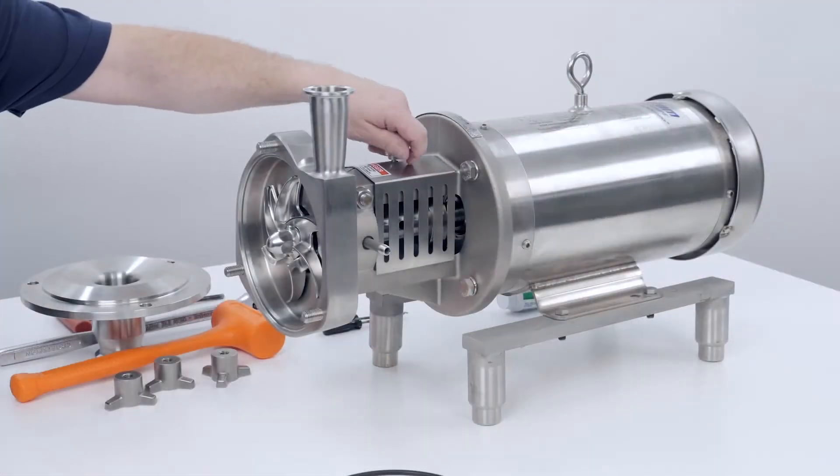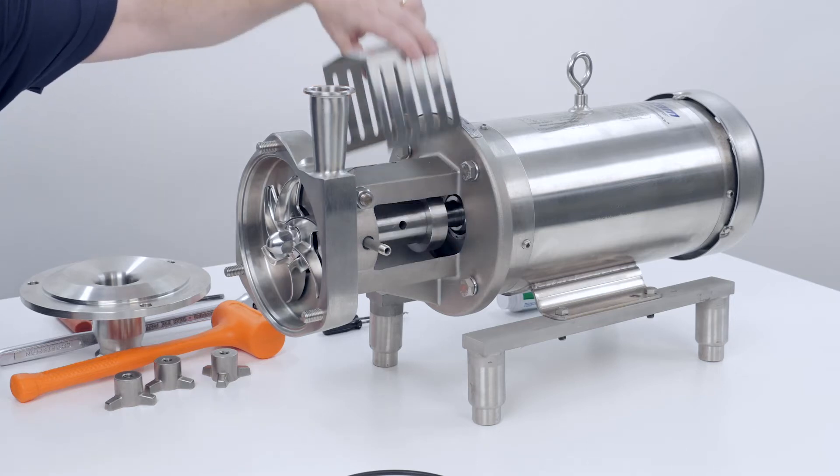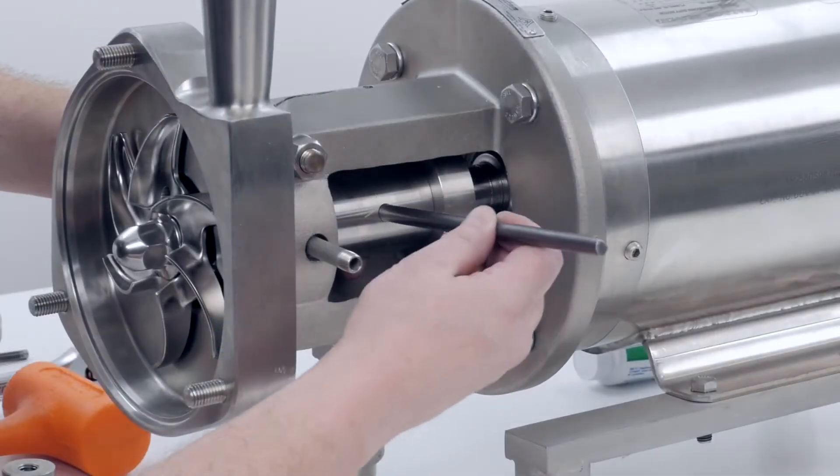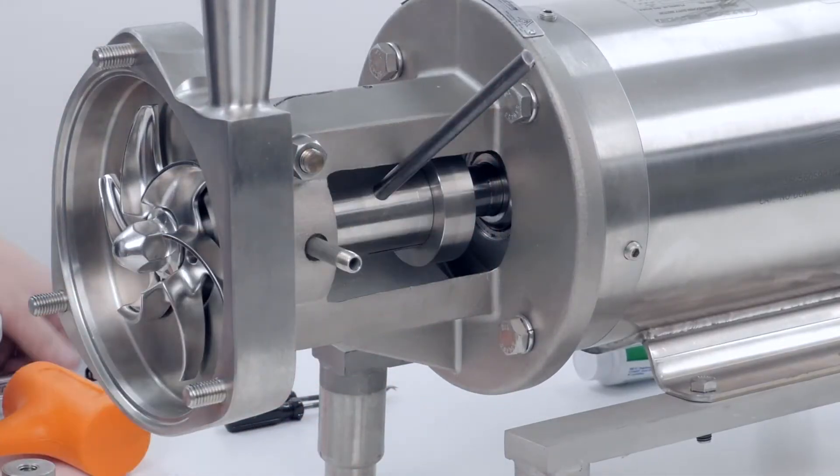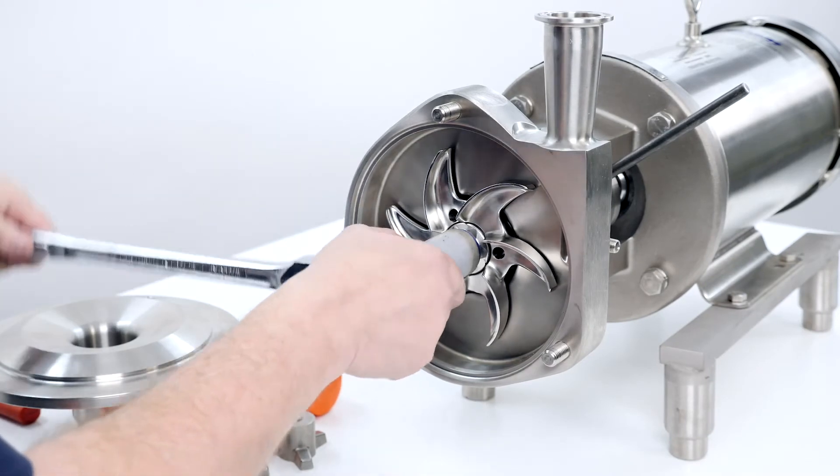Remove the flange guard. Place a 3/8 inch rod in the shaft hole to stop shaft rotation. Use a 24 mm socket with ratchet to remove the impeller nut.